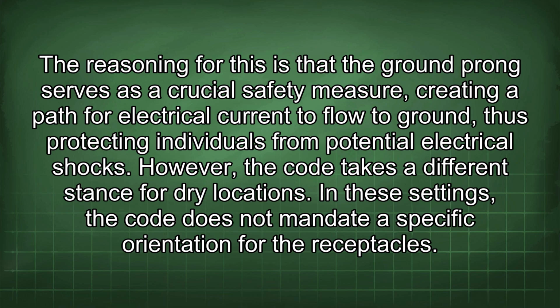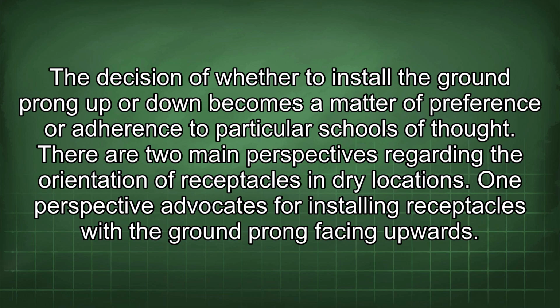However, the code takes a different stance for dry locations. In these settings, the code does not mandate a specific orientation for the receptacles. The decision of whether to install the ground prong up or down becomes a matter of preference or adherence to particular schools of thought. There are two main perspectives regarding the orientation of receptacles in dry locations.